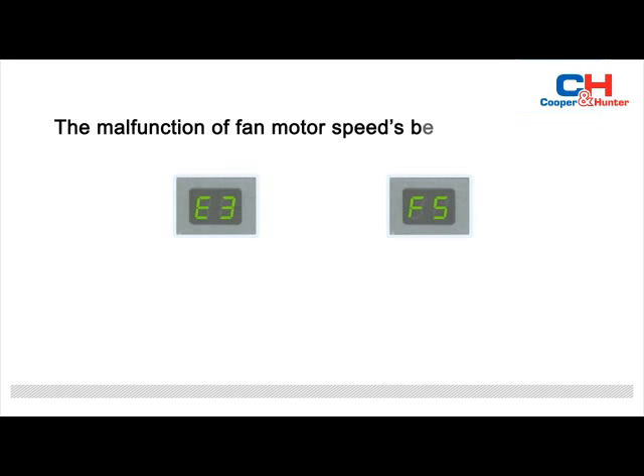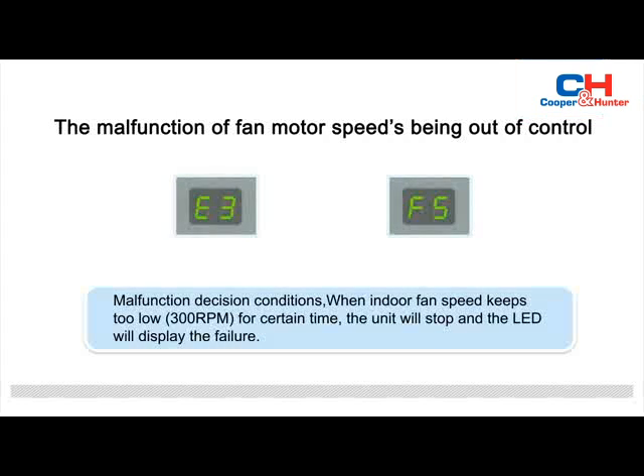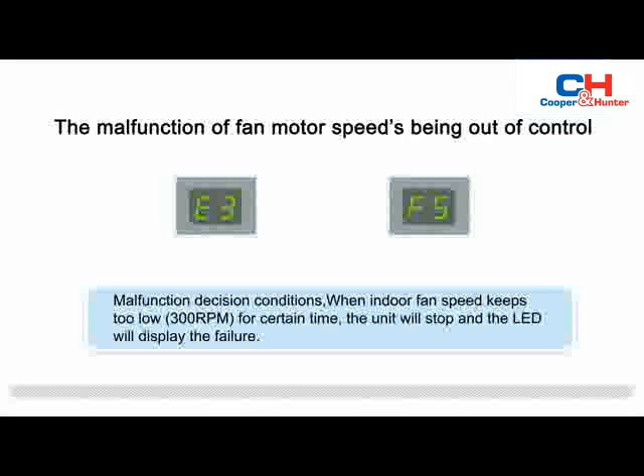When the display board of the indoor unit displays E3 or F5, that indicates the malfunction of fan motor speed being out of control. Malfunction decision conditions: when indoor fan speed keeps too low — below 300 RPM — for a certain time, the unit will stop and the LED will display the failure.